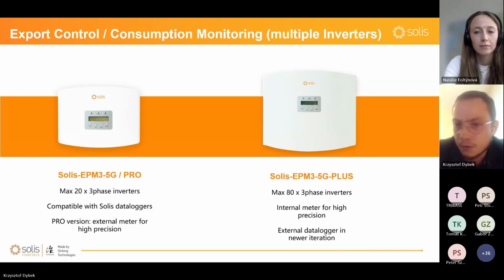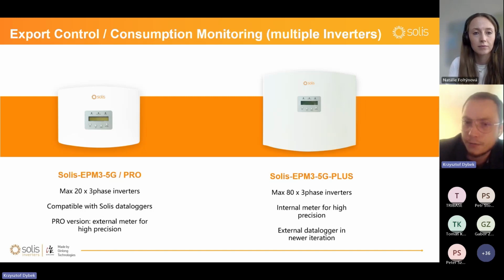We have a variety of options there. You can use a typical cascading scenario when RS is going out of the EPM and goes to input in this inverter. Then from this first slave is going out to the next one, and so on, etc. Another option is using star type. And so you are connecting all inverters to EPM to the same port. In short, if all A and all B are connected to each other, there is no problem. A, of course, means plus, B.